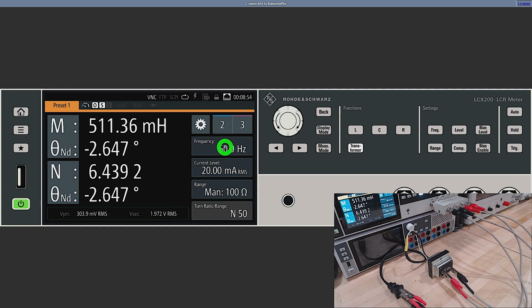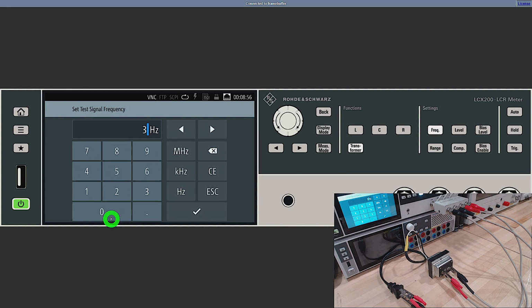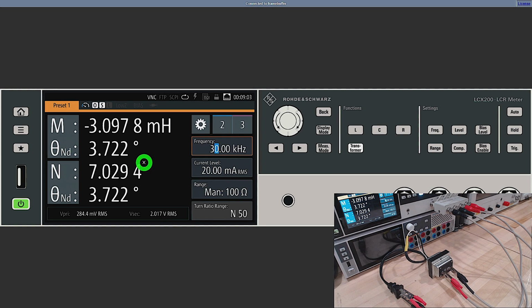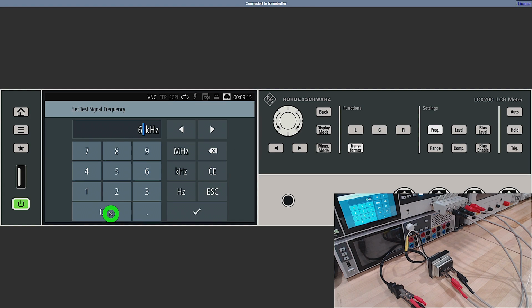Now what happens if I increase the frequency? Well, let's go all the way to 30 kilohertz, which is well above the frequency where this inductor transformers are intended to operate. What do we get? Look what happens. Your mutual inductance becomes negative, and this is an immediate indication that we are past the resonance frequency of this transformer. It's not going to work very well at this frequency. It's a good quick test to make sure you're operating it in a favorable region.